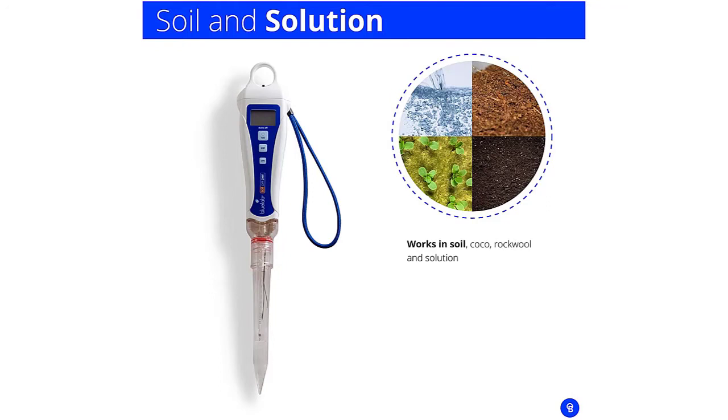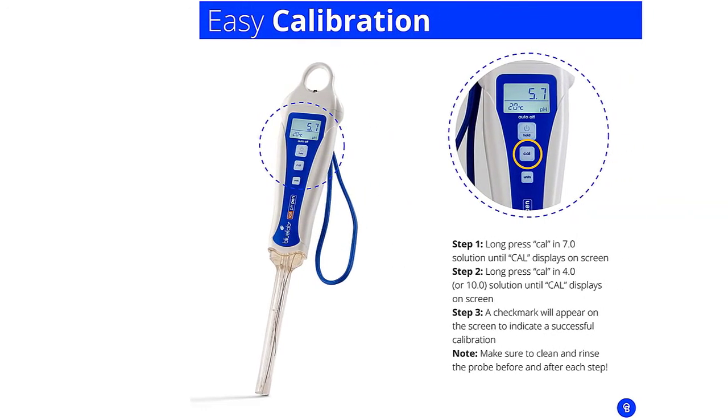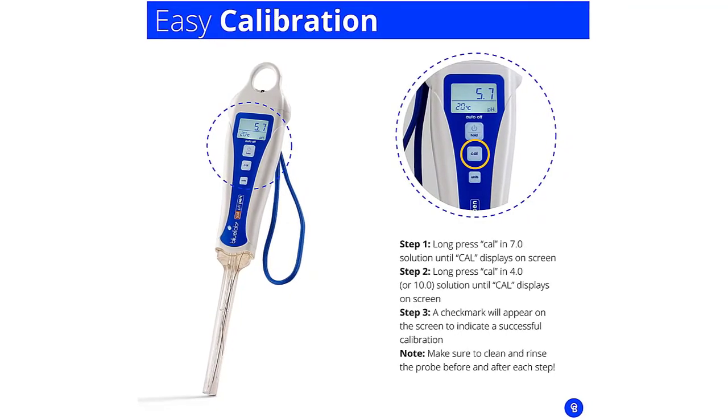All you need to do is dip the meter in water, give it a stir, and watch the numbers lock in on the easy-to-read backlit LCD screen. You'll then get an idea of what your water quality is really like. Its conductivity range is 0–9,990 µS/cm. The temperature range is 32 to 176 degrees Fahrenheit and 0 to 80 degrees Celsius.